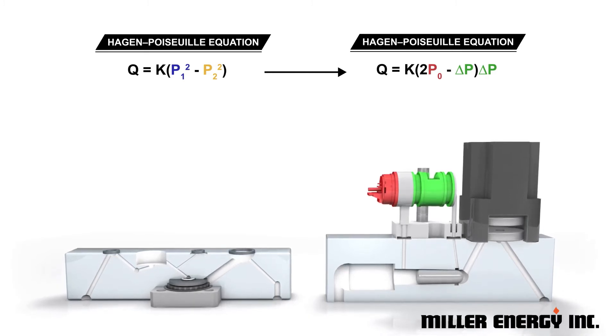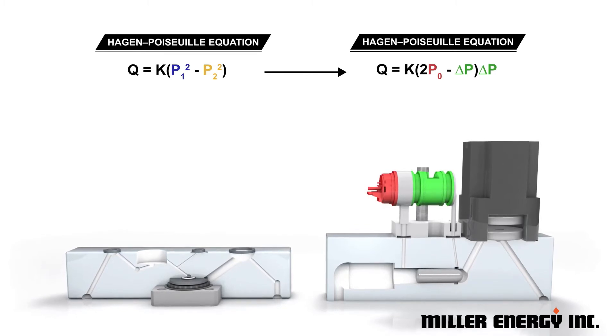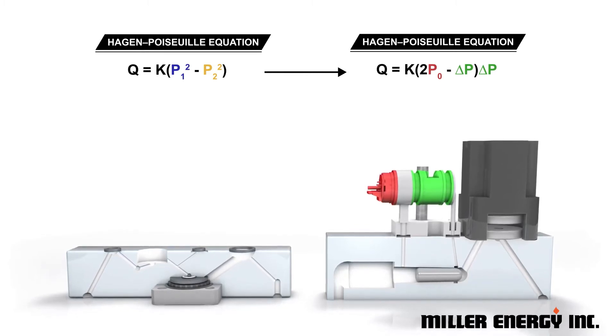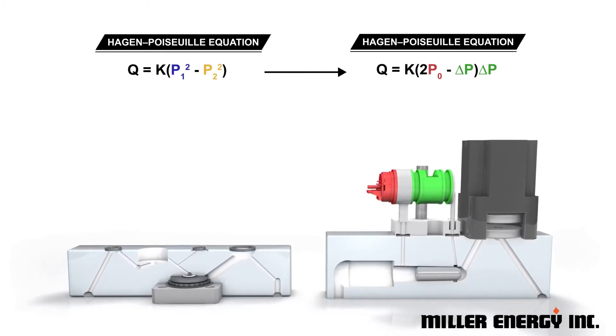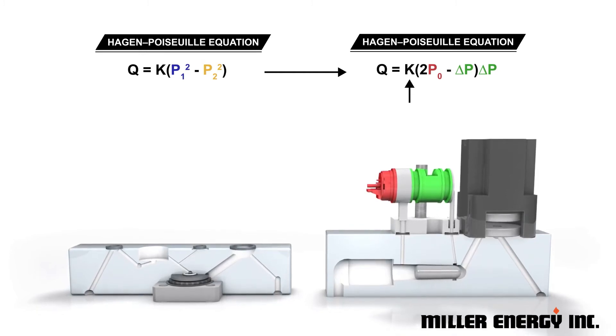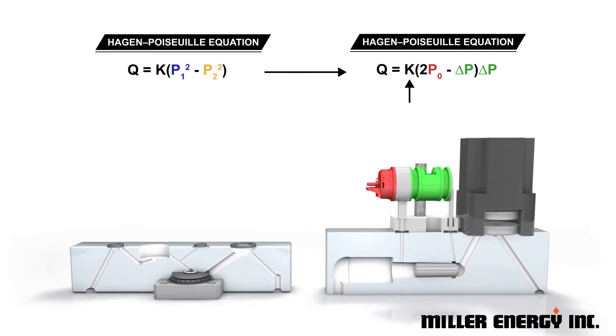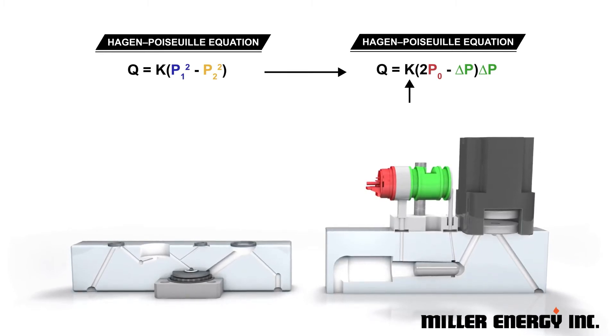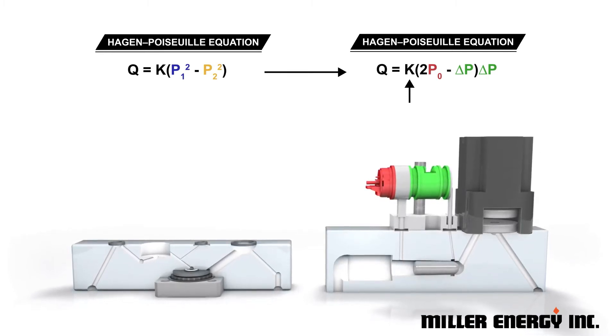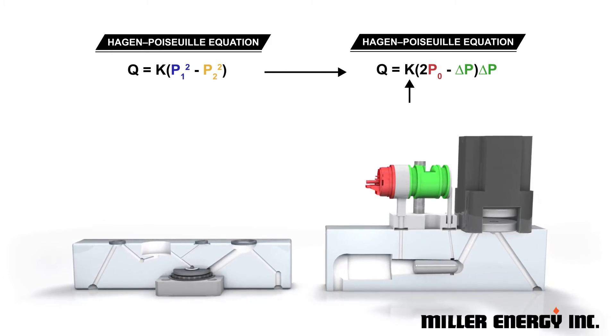This reduces measurement uncertainty and improves accuracy, particularly for critical low-vapor pressure process gases. The K-factor in the equation is an empirical constant dependent on the temperature, viscosity, and compressibility of the gas, and the geometry of the laminar flow element.